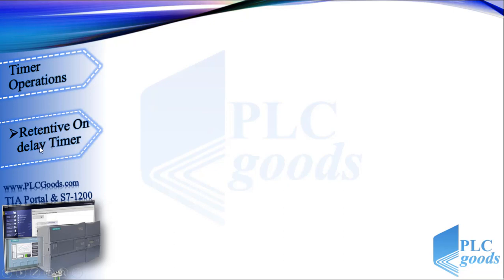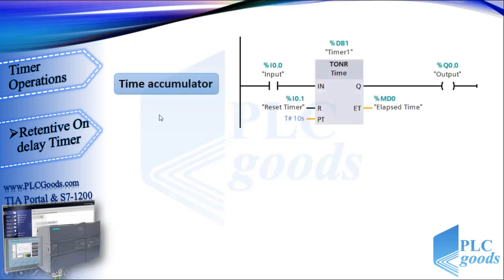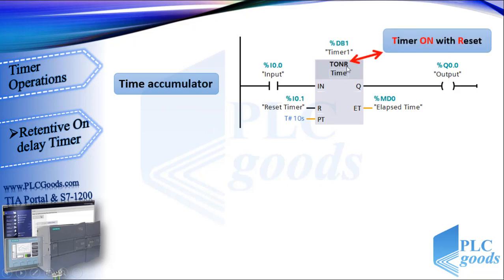Let's start with the retentive on-delay timer, or time accumulator. This instruction is used to accumulate time values when its IN input is activated. We can notice this timer with TONR syntax — it means Timer On with Reset — because this timer has a reset input. Otherwise its inputs and outputs are like previous timers.